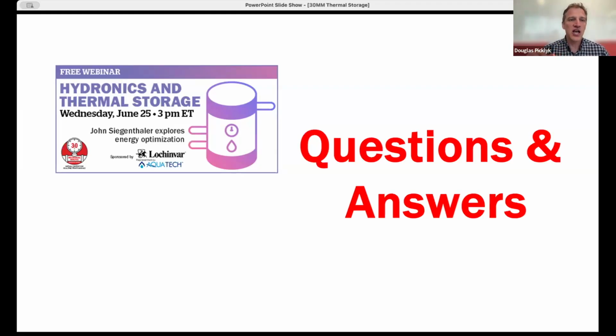The whole system's using glycol. That would be, or an alternative, it could work on water. That's a very interesting kind of side topic. There, air to water heat pumps in the European market. There are thousands of heat pumps that are air to water that are running on water without any antifreeze, and they do use freeze protection valves. These are thermostatic valves that would open and drain water from the heat pump during a power failure.